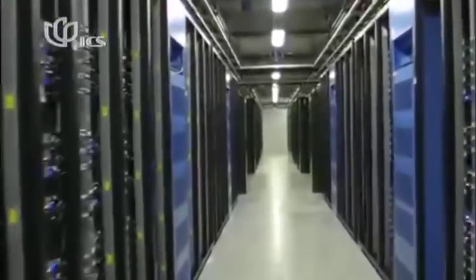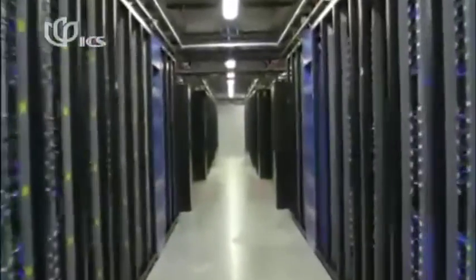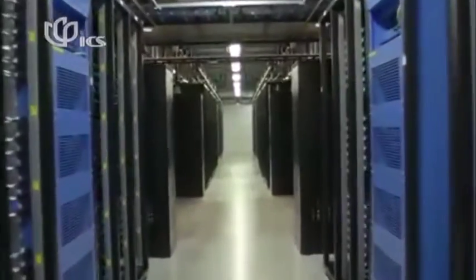Most of that extra goes into cooling systems, and internet companies are having trouble keeping up. The challenge is the power use and the cost to cool that room. In China, what we've typically seen is that fewer servers are used per rack to address cooling inefficiencies. So typically we see around 3 kilowatts, which is fairly low density, but the industry trend is toward higher density per rack, moving to 5 kilowatts, 7 kilowatts, and beyond.